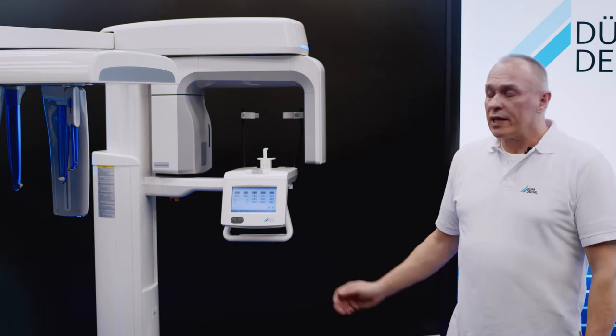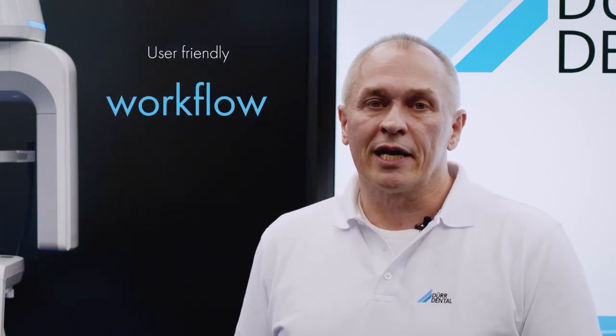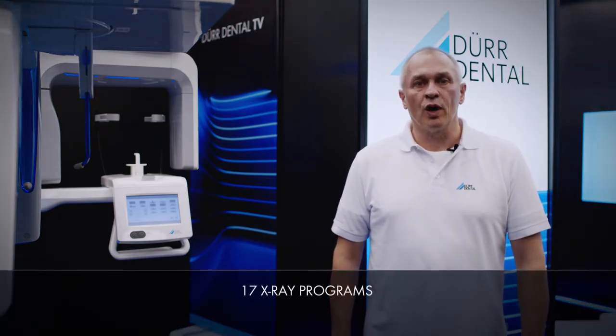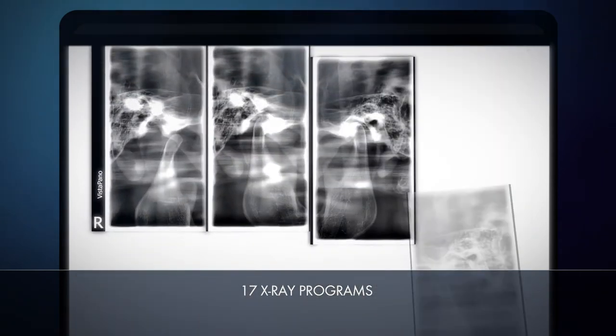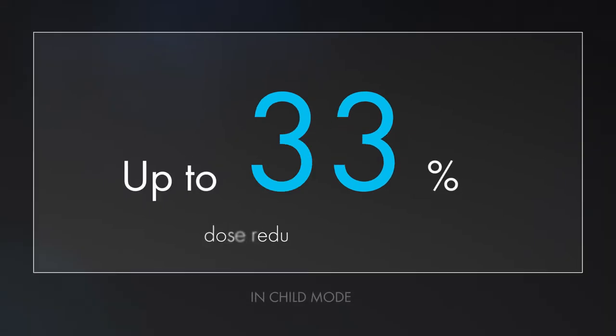The seven-inch touch display visualizes all settings. Handling and navigation are exceptionally user-friendly, making the process of taking x-rays a smooth one. With 17 x-ray programs, every diagnosis is catered for. When taking images of children, the smaller exposure area and fewer x-ray parameters reduce the dose by up to 33% compared with x-ray images of adults.